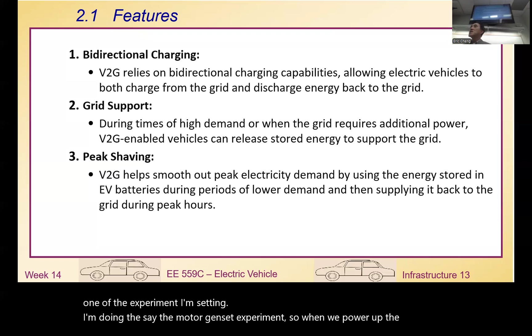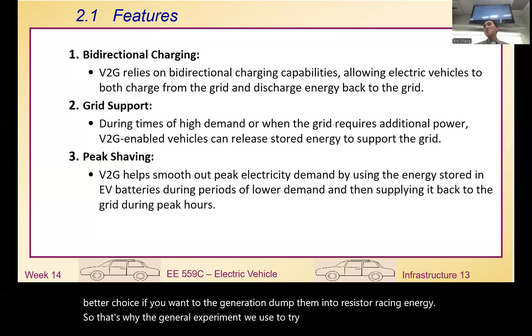So even in the lab, when we do experiments, we can also feed our power back to the grid so we don't need to dump the system. Like one experiment I'm setting up, the motor genset experiment: when we power up the motor, it becomes a generator, and this power will feed back into the power grid. That's a much better choice—if you dump the generated power into a resistor, that's wasting energy. So for generator experiments, we usually try to push the energy back to the power grid to feed into our building distribution system.